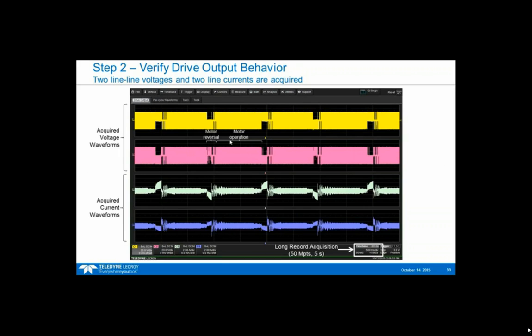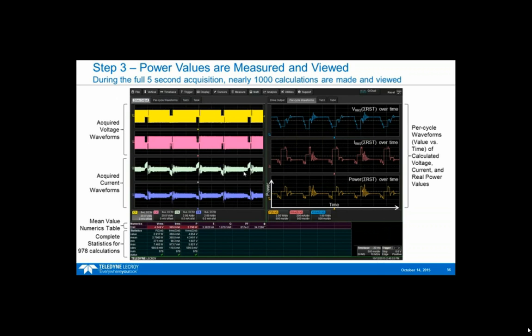And what we have right here, this is the motor reversal area. This is the motor operation, and then repeating 5 times throughout this waveform. We're going to show now a zoom of what that looks like. But first, for this 5-second acquisition, same data set right here, what the customer did was look at the RMS voltage for the drive output, the RMS current for the drive output over time, and the power of the drive output over time. So for instance, in this case, power is the vertical scale, time is the horizontal scale.